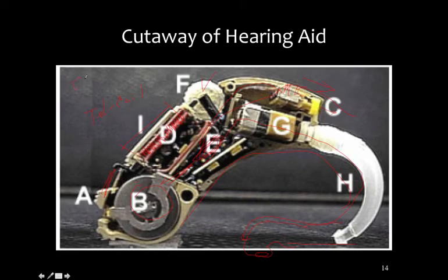If you've looked at the HLAA stuff, they're talking about the looping of America. With the loop, a copper loop in a room generates electromagnetic energy, and that would be picked up by this. So if a person's wearing a hearing aid and they know that a room is looped, they flip this switch to the T setting for telcoil. Now the talker in the room is speaking through a system which is also generating an electromagnetic signal. This thing picks it up. So it's an advantage for the person to have this in their hearing aid, and you'll see that a number of recommendations include that.